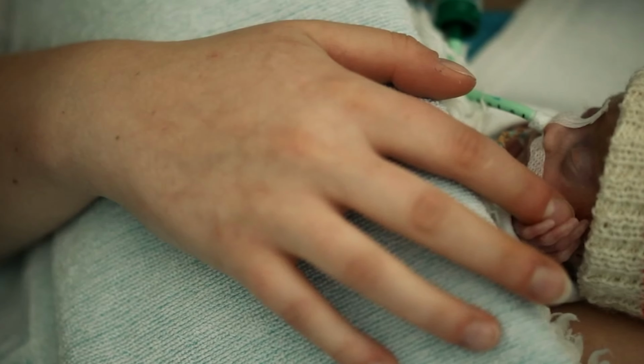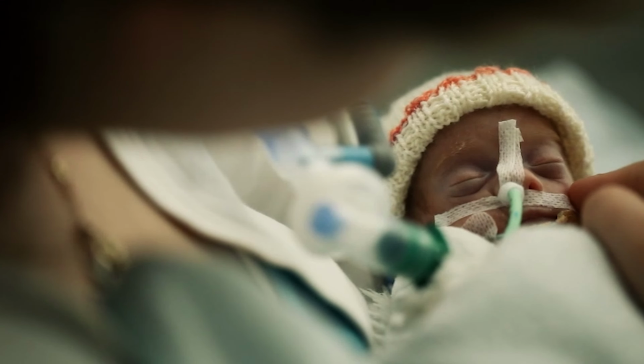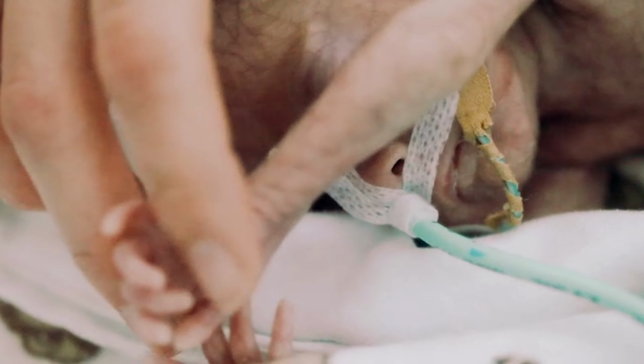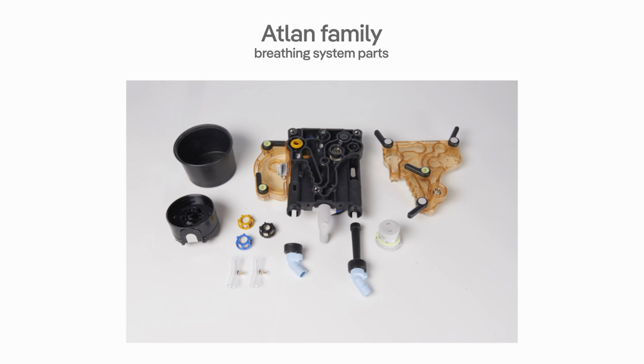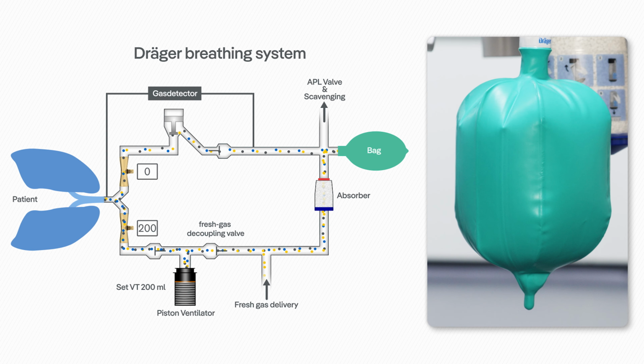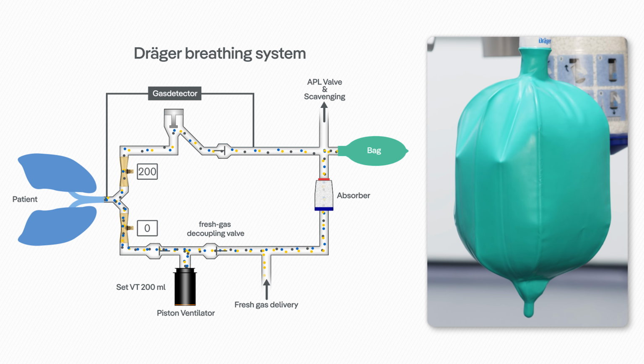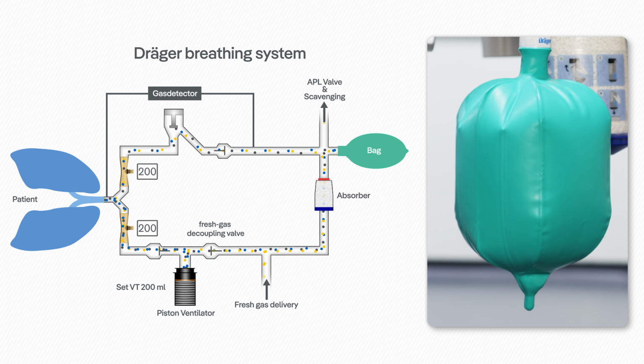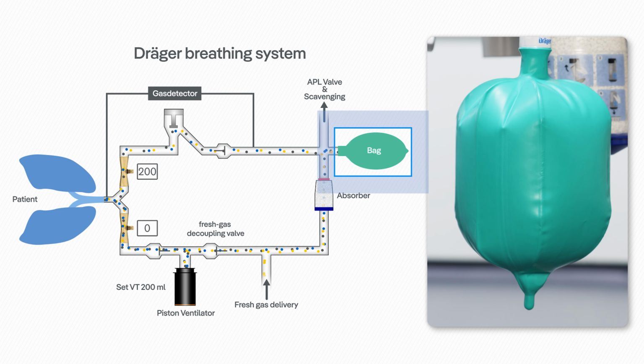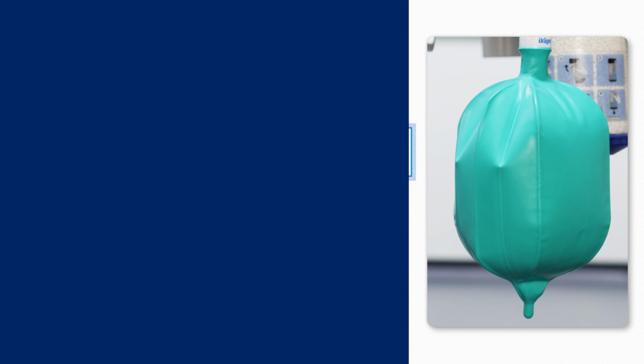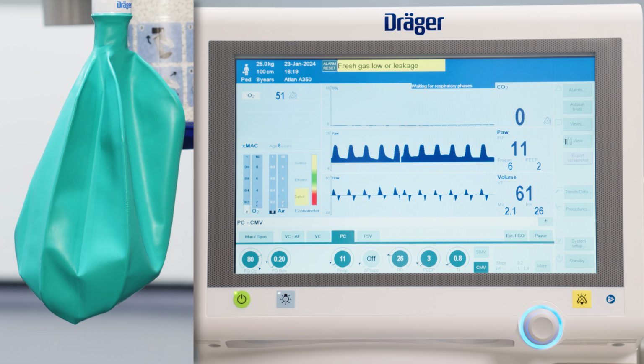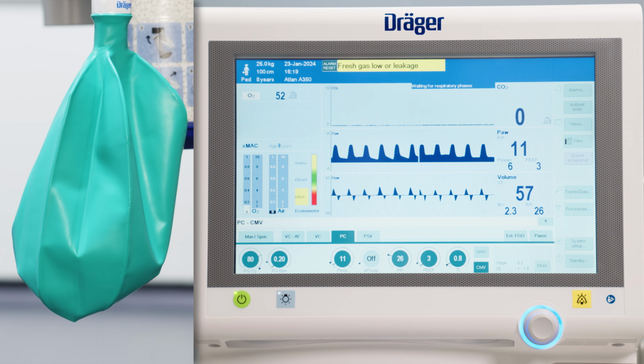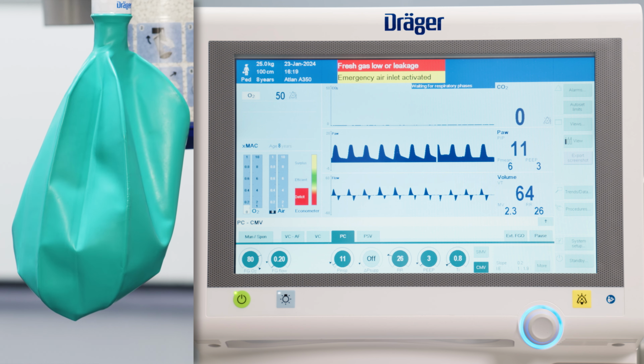The breathing system of the anesthesia device has to be as tight as possible to minimize system leakages, which can have an impact on delivered tidal volumes. The breathing systems of all Atlan family anesthesia machines consist of only a few parts to reduce the number of connections for potential leakages. And unlike other anesthesia systems, the breathing bag in Atlan family anesthesia machines is an integral part of the breathing system that acts as a fresh gas reservoir and indicator for adequate fresh gas flows. An empty breathing bag indicates a fresh gas deficit, and that the fresh gas flow needs to be increased.